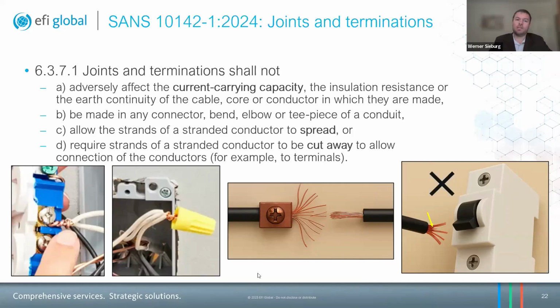Now, the problem with that is that you're relying on the spring loadedness of the connector or the material, the copper. Over time, with vibrations, thermal expansion and heating, all those things can change the material properties and the spring loadedness. So the two helically wound conductors can become loose from one another, particularly if one doesn't make sure that either the screw, or on the right hand side this ceramic cap, actually holds them in place and that they remain in place.